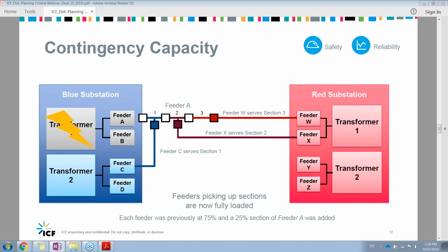Going back to the philosophy of each feeder being loaded to 75% maximum during peak load, that comes into play here when picking up an individual section. One of those 3 sections is going to add 25% to that previous 75%, and again this is at absolute peak, which is how the system is typically planned for.